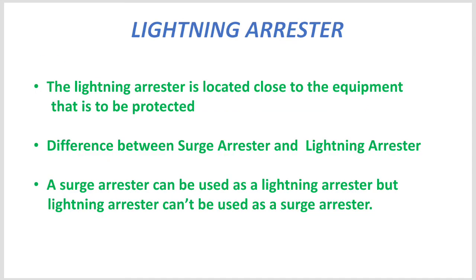In transmission and distribution, surge arresters and lightning arresters are used in 2 major departments — they are essentially 2 names for similar things. Surge arresters are installed inside the panels, while lightning arresters are outside the components. The major role of a surge arrester is to protect electrical installation and equipment from electrical surges and transient voltages caused by electrical faults, switching, circuit breakers, sparks, and lightning. Surge arresters are installed inside the panel to cancel out surges.